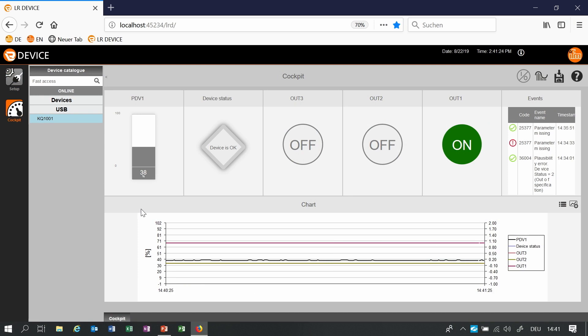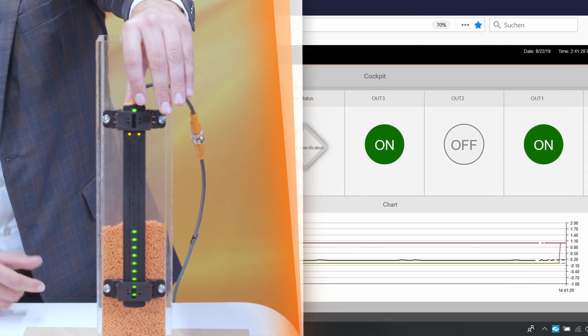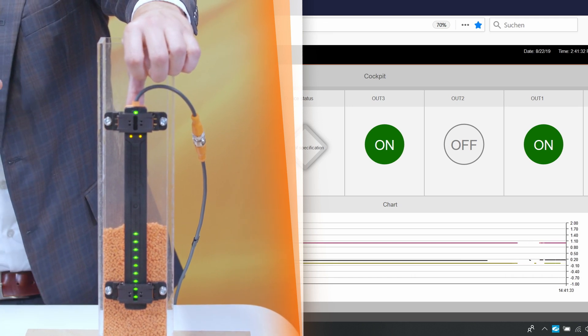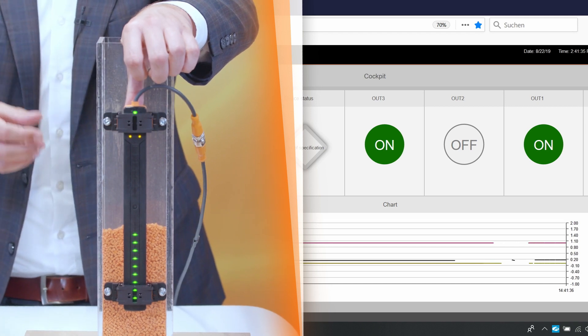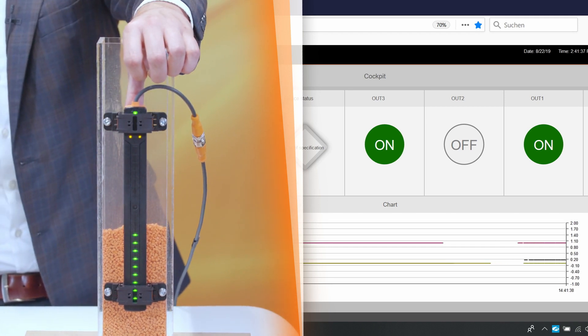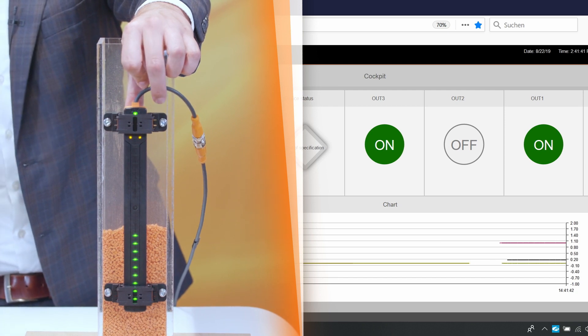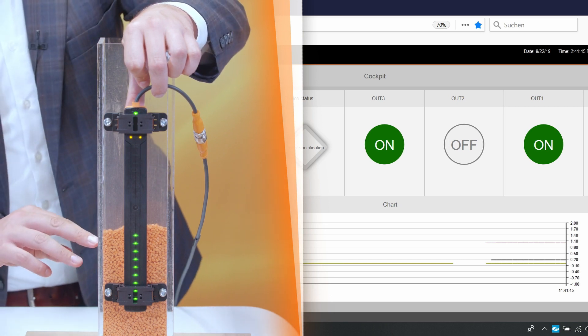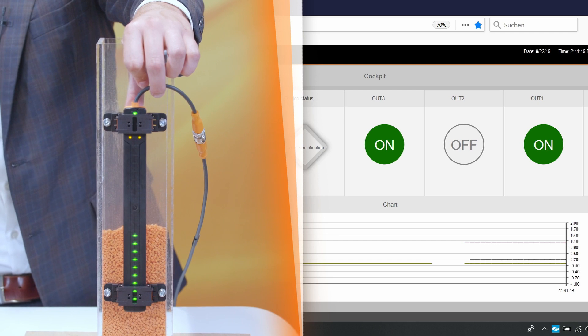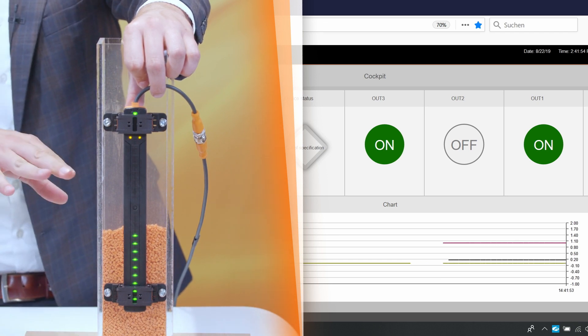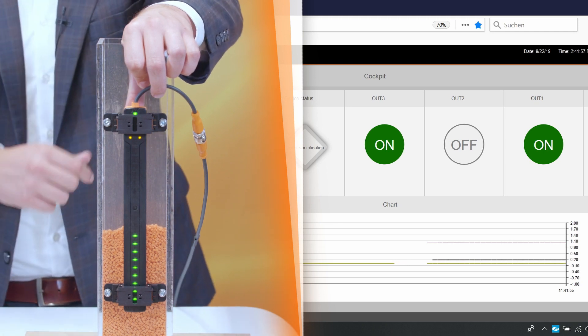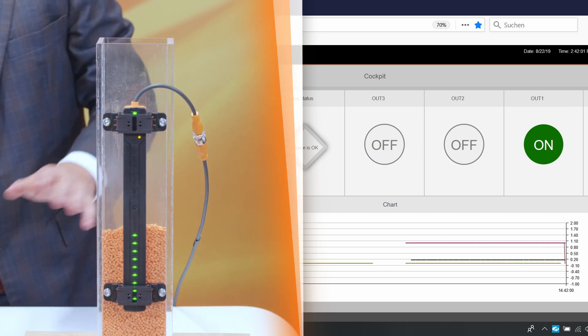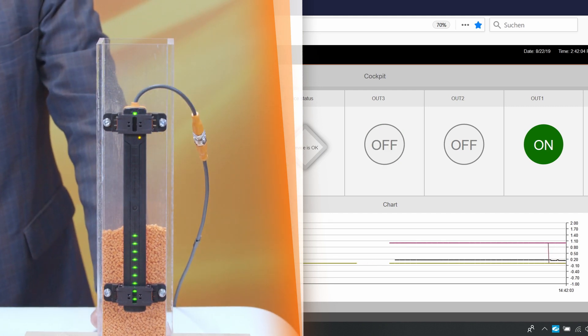So when I touch the sensor or the tank over here the third switch point will switch on. This is for safety because when the level is rising and the sensor gets disturbed in any way this switch point will be on and the application is safe. The level inside here will stop so we will have continuously in this case 39% of the filling level but the switch point will switch on. When I remove my finger the sensor is working as it worked before.